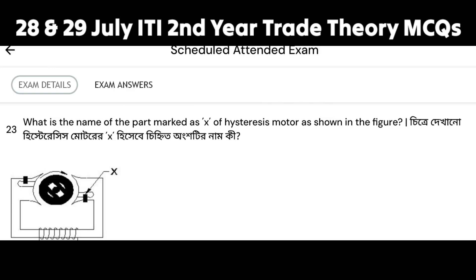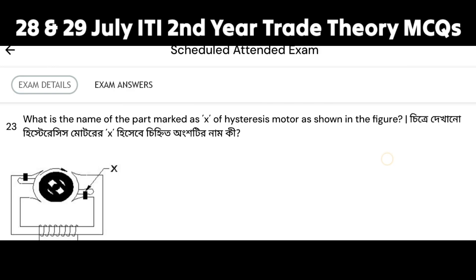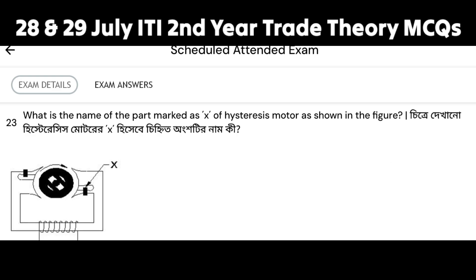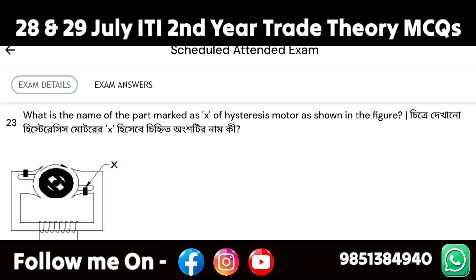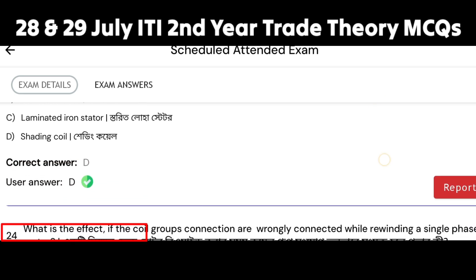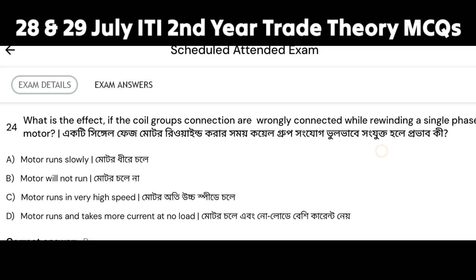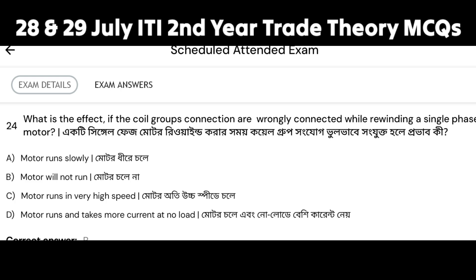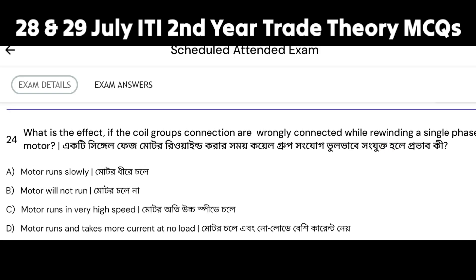What is the name of the part marked as X of the hysteresis motor? Next question: what is the effect if the coil groups are wrongly connected while rewinding a hysteresis motor? The options are: motor runs slowly, motor will not run, motor runs at very high speed, motor runs and takes more current at no load. When connected wrongly, the flux direction is opposite, so the motor will not run. Option B is the correct answer.